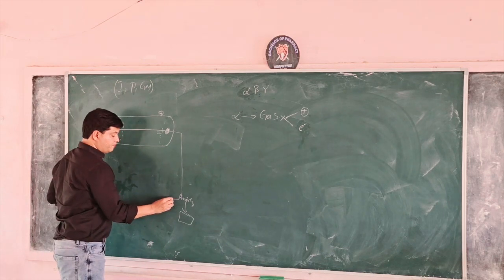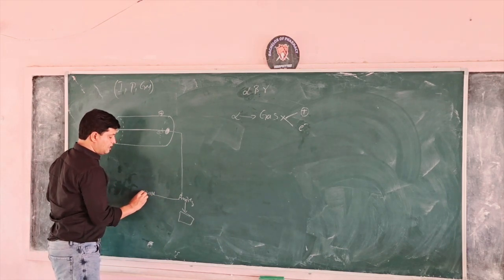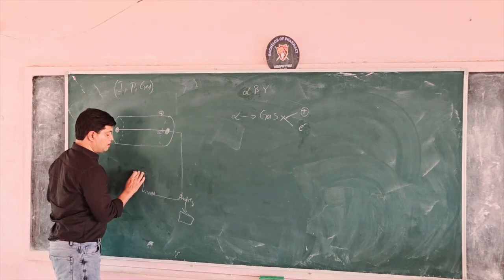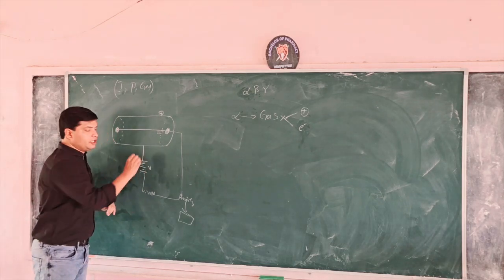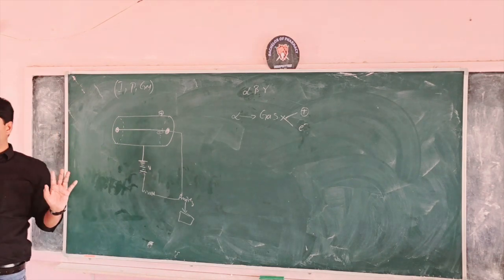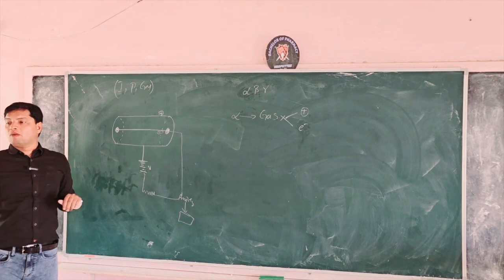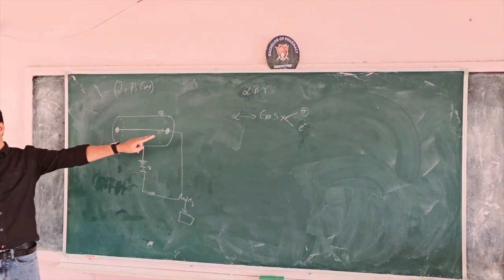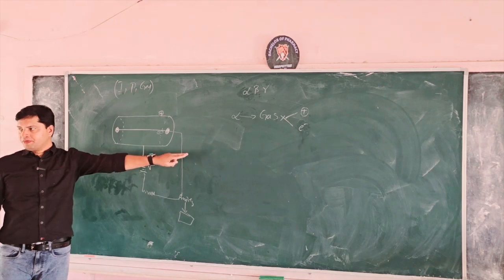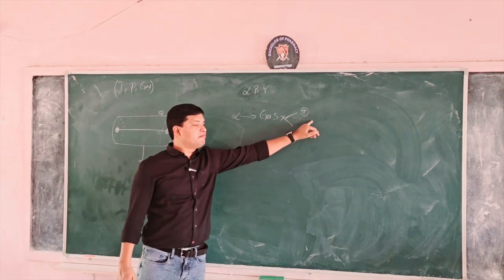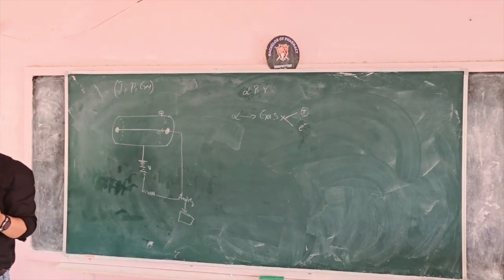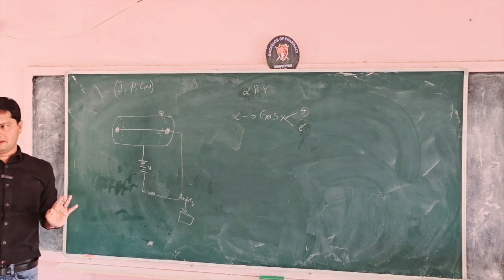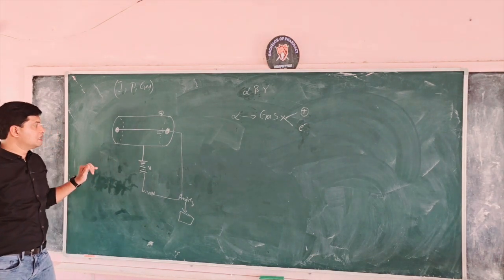Here we have a resistor, then we have something which can induce the voltage. Remember the construction. Now, what is the principle here? Ionization of gas molecules is the principle. If I ionize the gas molecule and can measure the amount of electron released due to ionization, then I can measure the amount of radiation. That's what the topic is.